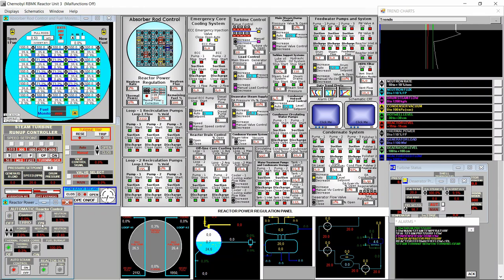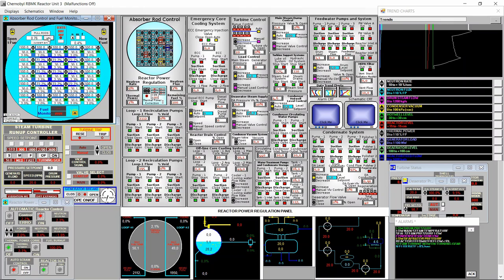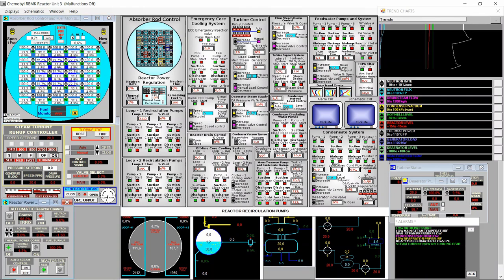I will hold at seven percent and then connect the automatic reactor control, which adjusts rods to keep a given power set point. The power set point is at two percent. I pull rods to engage the automatic control, but it goes to four percent so it's not in auto. I increase the set point to five percent to match and see if it engages auto.